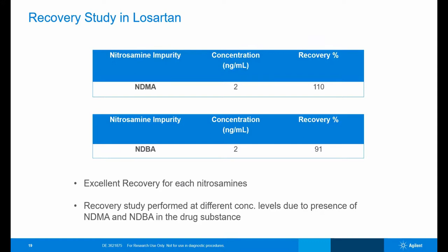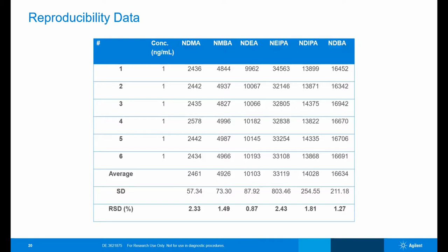Another important thing to understand about method ruggedness is its reproducibility data, and if you see here we got excellent RSD percentage for all 6 nitrosamines for 6 replicates at 1 nanogram per ml concentration. And here is the RSD percentage value with bracketing standards also considered in the calculation. Again, you can see all 6 nitrosamine impurities are showing less than 6% RSD, which is very good at this concentration level.